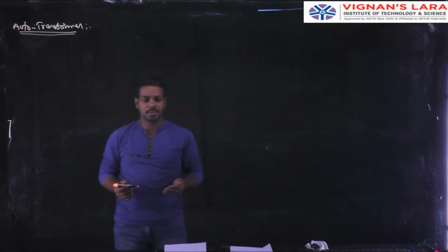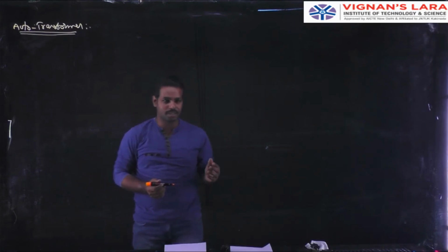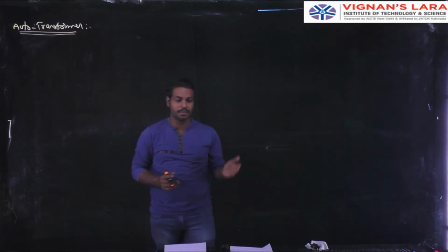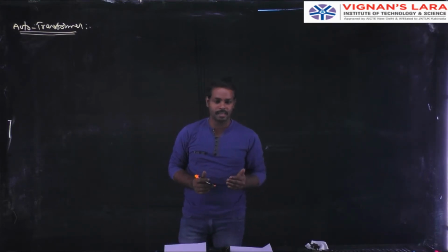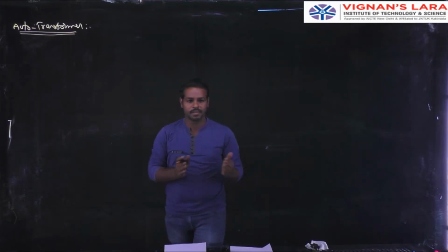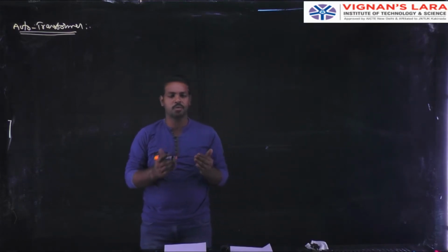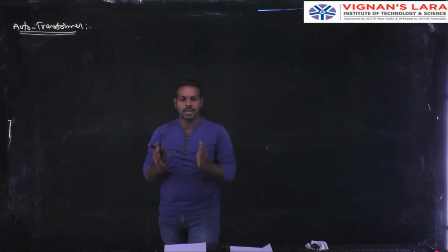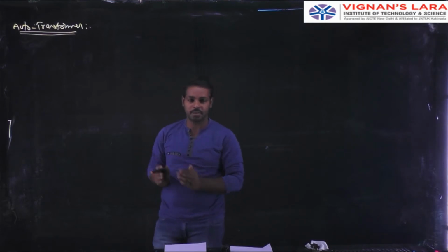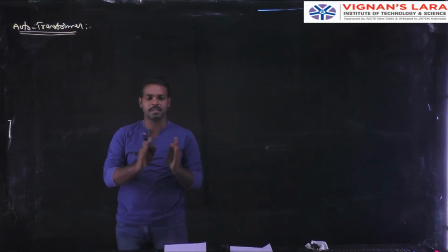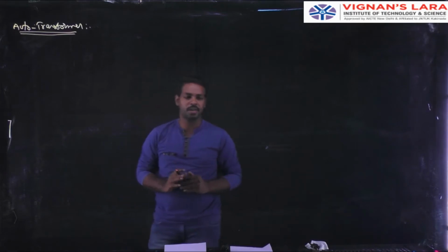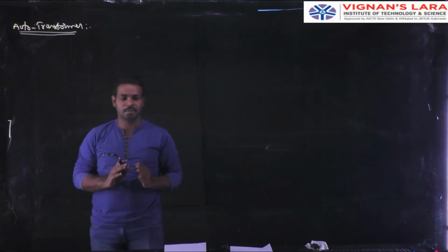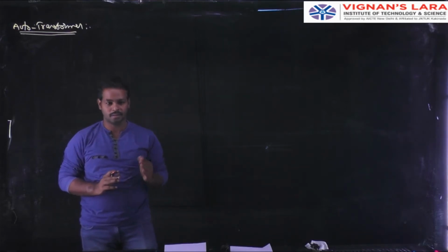In an auto transformer, less copper is required to change the voltage levels. But an ordinary transformer has a primary winding as well as a secondary winding, which requires more copper. Another point is that the auto transformer is compact in size, but an ordinary transformer is larger for the same voltage rating. These are the general differences between an ordinary transformer and an auto transformer.